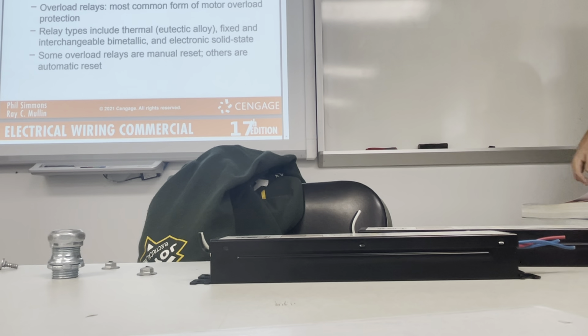Motor overload protection. Proper protection protects motor branch circuit conductors from overheating. Overload relays, most common form of motor overload protection. Relay types include thermal, fixed and interchangeable bimetallic, and electronic solid state. Some overload relays are manual reset, others are automatic reset.